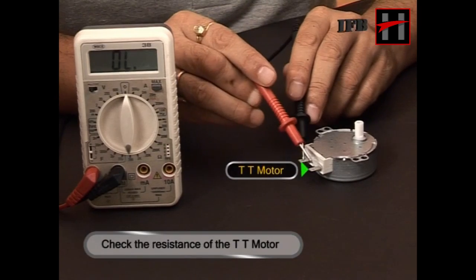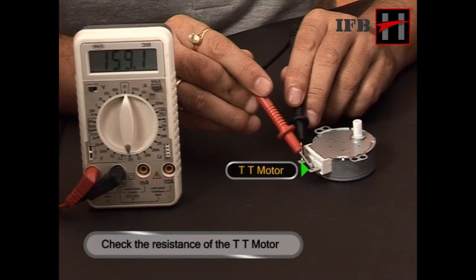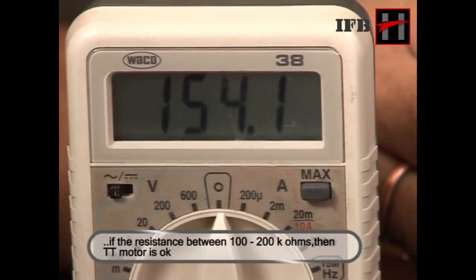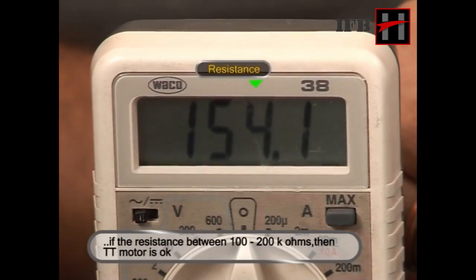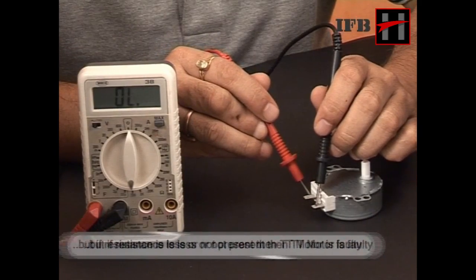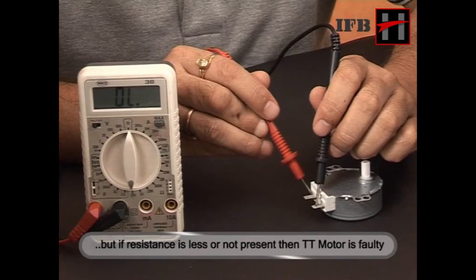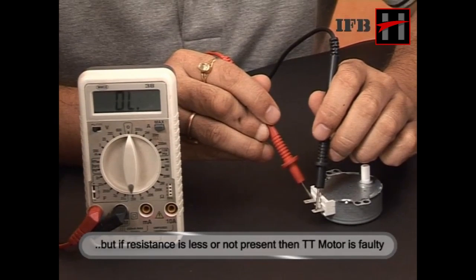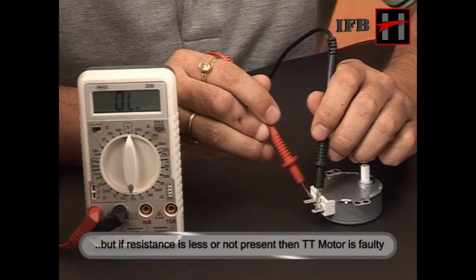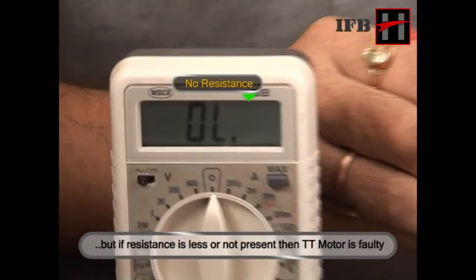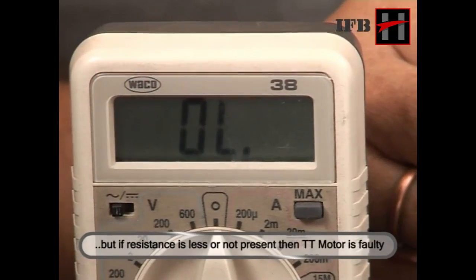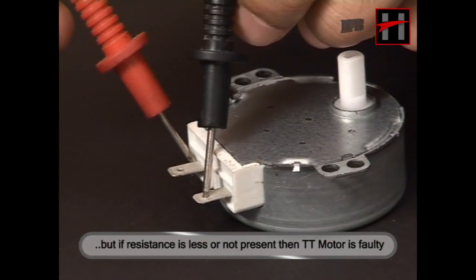Check the resistance of the turntable motor or the TT motor. If resistance is between 100 to 200 kilo ohms, then turntable motor is OK. But if resistance is lesser than 100 to 200 kilo ohms, or if resistance is not present, then the TT motor is faulty.